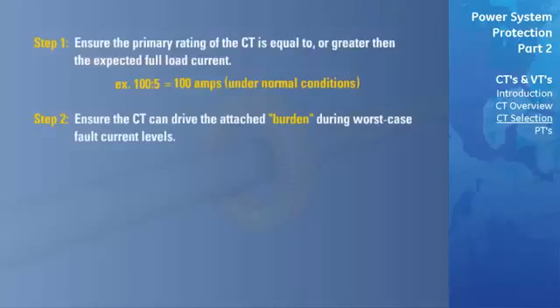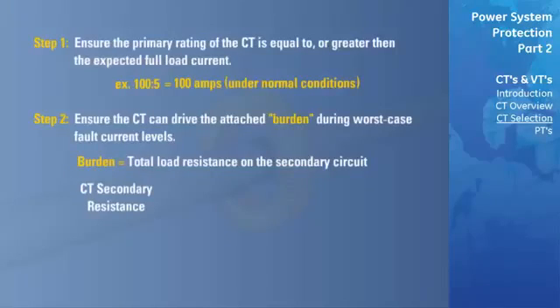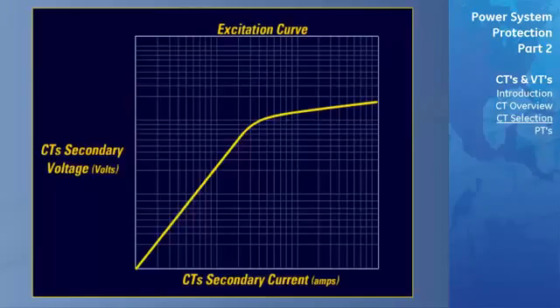The second step is to ensure that the CT can drive the attached burden at the worst-case fault current levels without saturating. The burden refers to the total load resistance of the secondary circuit. The calculation for the burden is CT secondary resistance, which is the amount of resistance on the secondary windings of the CT, added to the connection wire resistance, which is supplied by the manufacturer, added to the relay's burden resistance, which is the resistance within the protection relay. A CT becomes saturated when the secondary voltage reaches the knee point of the excitation curve.